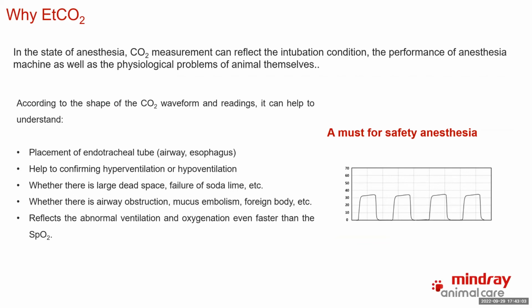So for example, you can tell a lot of things from the shape of the CO2 waveforms, like the intubation condition. We're talking about the placement of the endotracheal tube. You should put the tube into the airway, but maybe you put it in some other places, which would be wrong. There will be no waveforms. So you can tell from the shape of the waveforms. And also the different shapes of the waveform can help to confirm if the patient is having hyperventilation or hypoventilation. And also for the anesthesia machine, for example, if there's a soda lime failure, or maybe the dead space is too large, you can also tell from the waveforms.